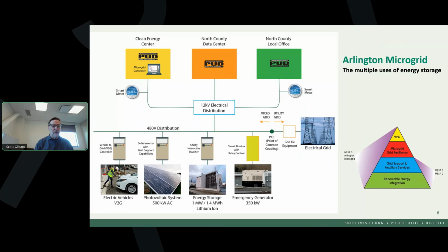So this microgrid currently is the backup power source for all of those different things if the grid goes away. Normally we're connected to the grid, as you can see, but if the grid goes away, we seamlessly disconnect, not a blink of the lights, which has been really, really hard to do. You need a grid forming inverter to do that.